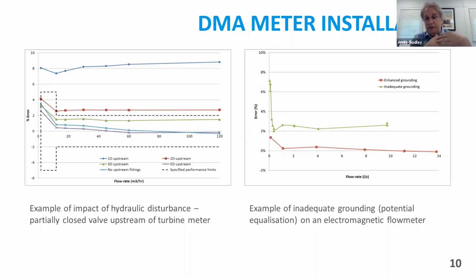So though we know that poor hydraulics can lead to deterioration in performance, we can't always predict what that will be. The graph on the right shows some very recent test data. This is from an electromagnetic meter that we are testing. It's a 50 mil meter, and we've been testing meters here for well over 20, 30 years, and we've never had a particular problem testing electromagnetic meters. We install them correctly, we look at our earthing and grounding and so on, and follow the manufacturer's instructions. And we tested this meter recently, and we're getting that green line at the top, a consistent 2% offset. And we thought, well, this isn't right. There's something going wrong here.